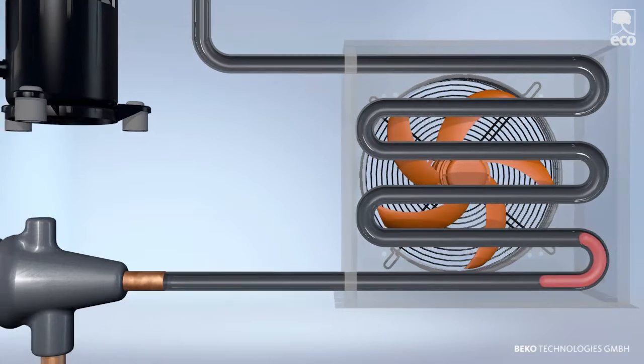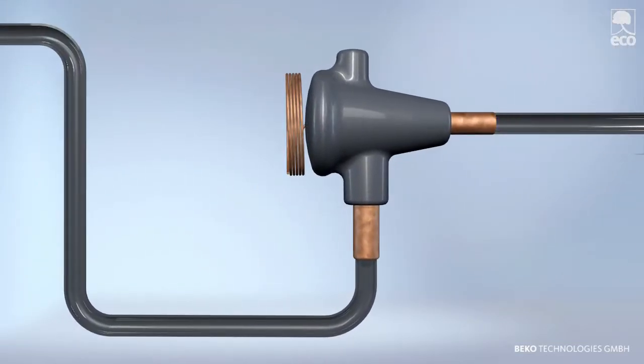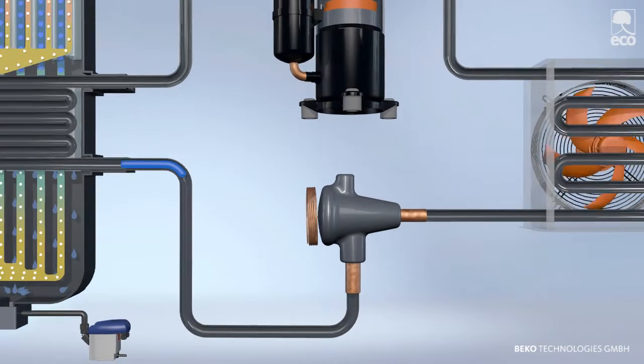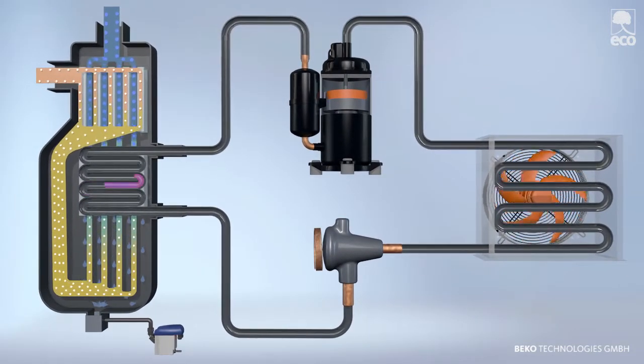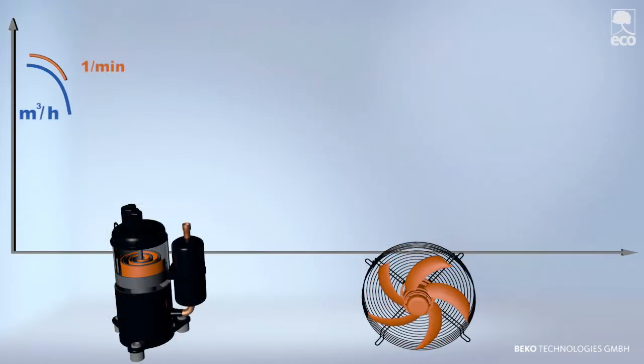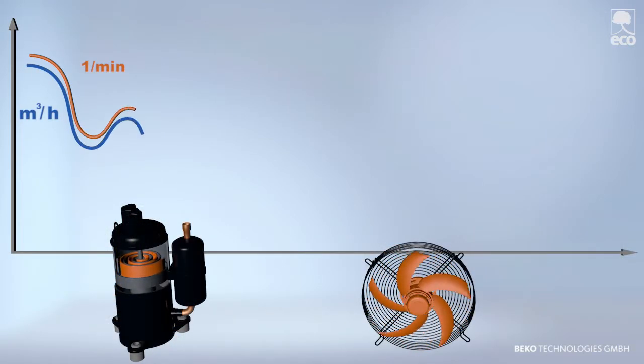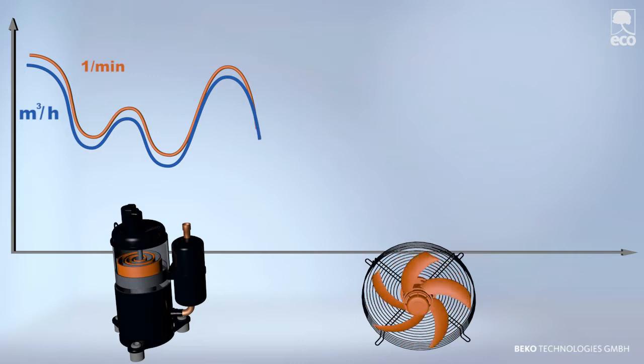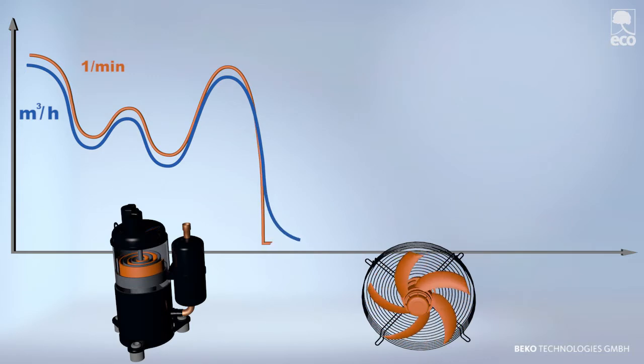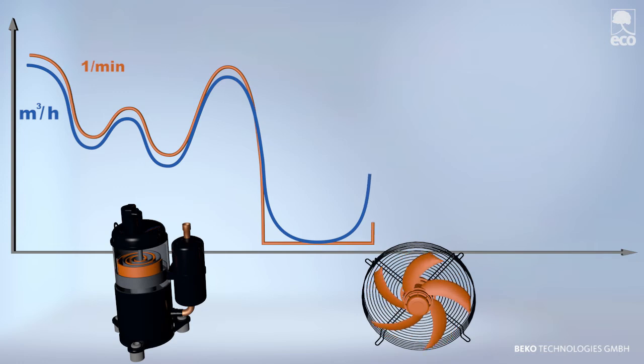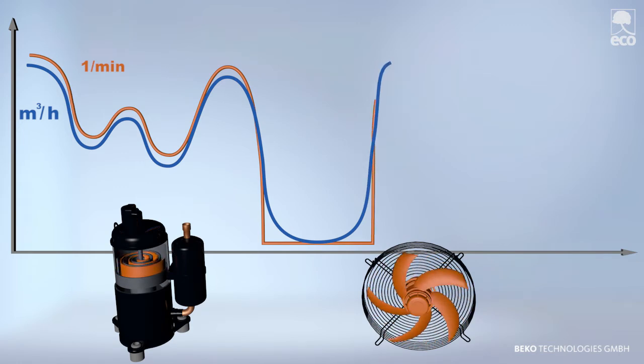Liquid, but still under high pressure, the refrigerant expands in the expansion device. The pressure decreases during this process, also resulting in a sharp decrease of temperature, which provides the heat exchanger with the necessary cooling capacity. The refrigerant evaporates and is drawn in by the compressor again, and the cycle begins once more. In order to save energy when fluctuations in compressed air occur, such as flow volume, temperature, or pressure, the smaller versions of the Drypoint RA Eco switch the refrigerant compressor on and off to accommodate variations in the drying requirements. After reaching a certain system size, the drying performance is controlled by changing the frequency of the compressor and thus even more finely adjusted to the volume flow.